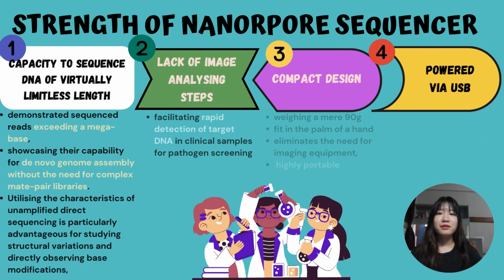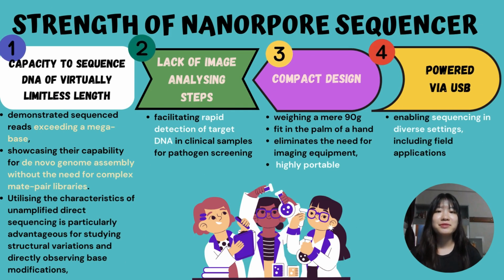One of the strengths of nanopore sequencers is the capacity to sequence DNA of virtually limitless length, with demonstrated sequence reads exceeding a megabase. Another strength is the lack of an image analysis step, thus facilitating rapid detection of target DNA in clinical samples for pathogen screening. Last, it is highly portable as it has a compact design and is powered via USB.